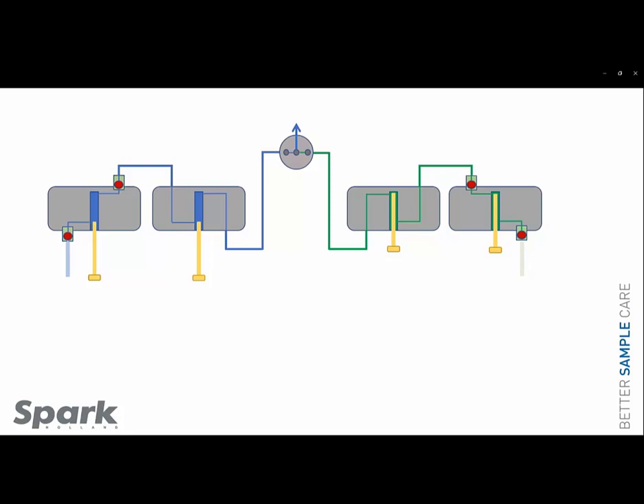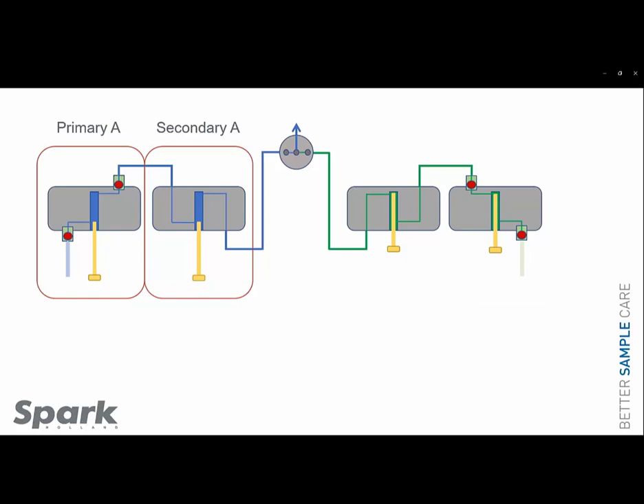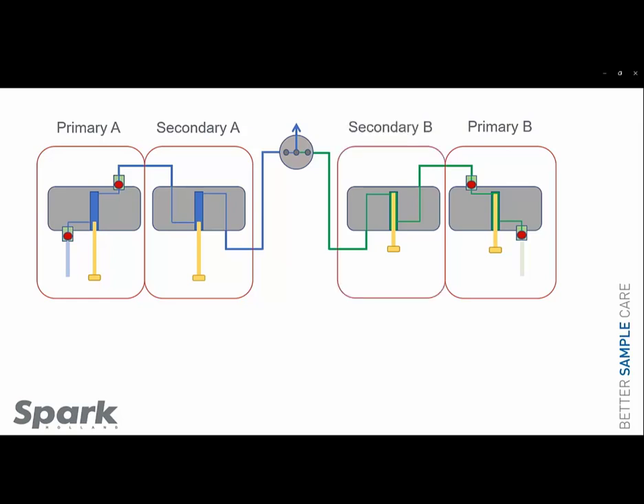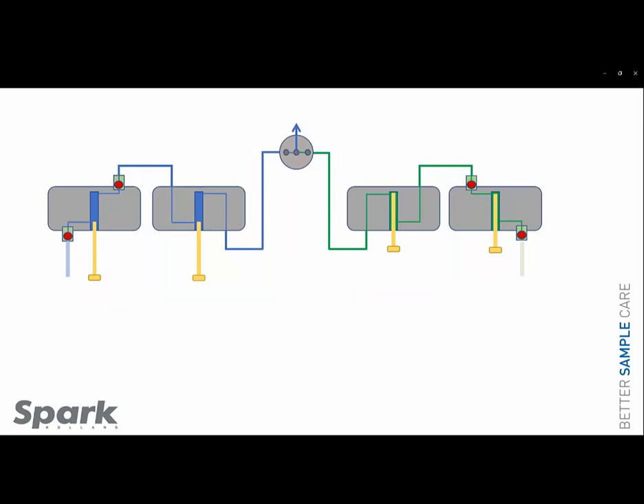Each pump has a primary pump head and a secondary pump head. Pump B has exactly the same configuration, a primary pump head and a secondary pump head. The primary pump head contains 2 check valves, one inlet check valve and one outlet check valve. The secondary pump head doesn't contain any check valve. Inside those check valves there's a cartridge. The cartridge is equal for both check valves, the in as well as the outlet.